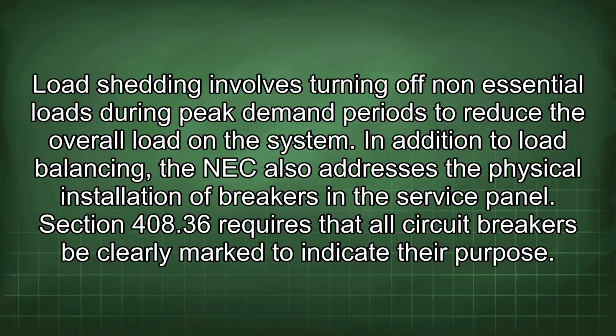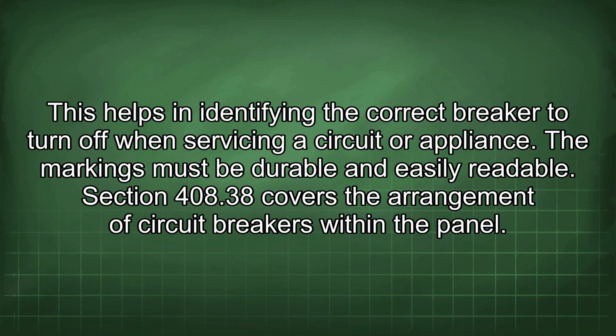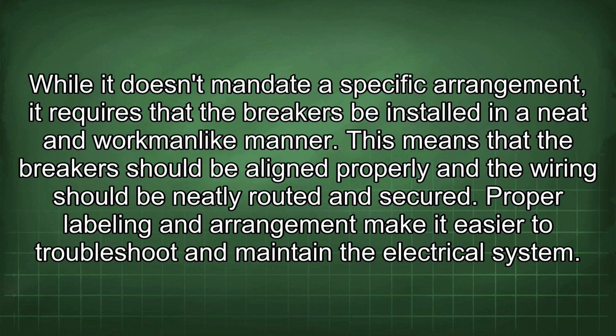Section 408.36 requires that all circuit breakers be clearly marked to indicate their purpose. This helps in identifying the correct breaker to turn off when servicing a circuit or appliance. The markings must be durable and easily readable. Section 408.38 covers the arrangement of circuit breakers within the panel. While it doesn't mandate a specific arrangement, it requires that the breakers be installed in a neat and workmanlike manner. This means that the breakers should be aligned properly and the wiring should be neatly routed and secured. Proper labeling and arrangement make it easier to troubleshoot and maintain the electrical system.